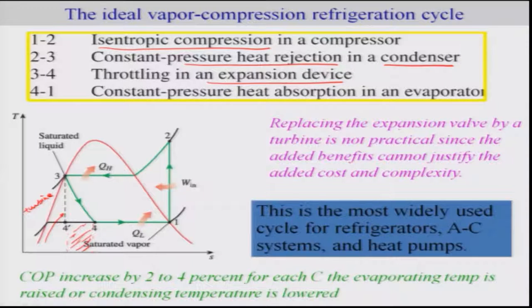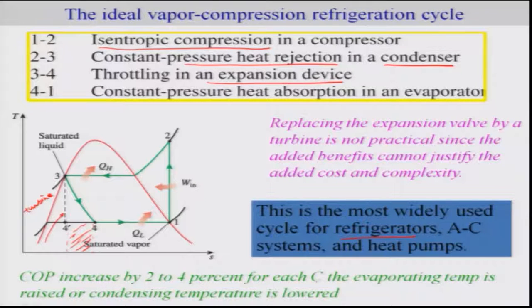This ideal vapor compression refrigeration cycle is commonly used for refrigerators, air conditioning systems, and heat pumps. It should be noted that the coefficient of performance increases by 2 to 4 percent for every degree Celsius the evaporating temperature is raised or the condensing temperature is lowered.